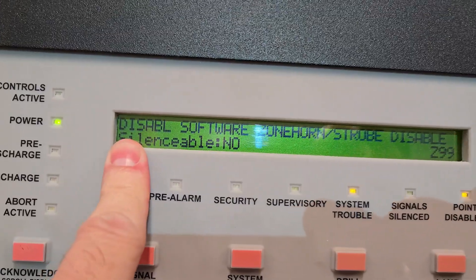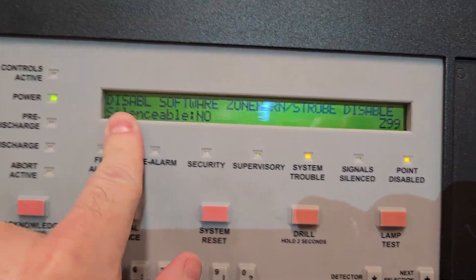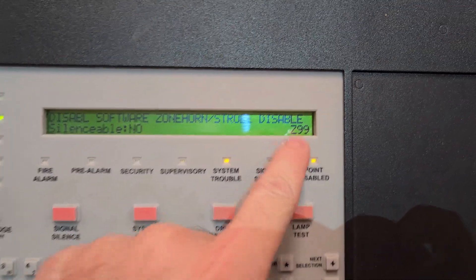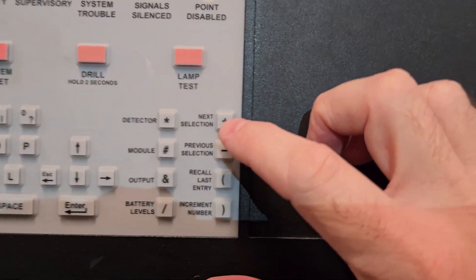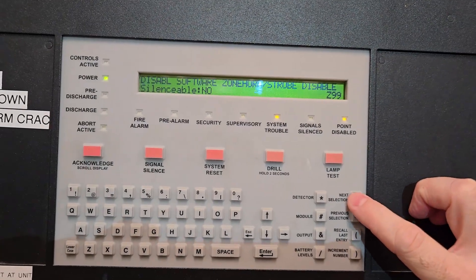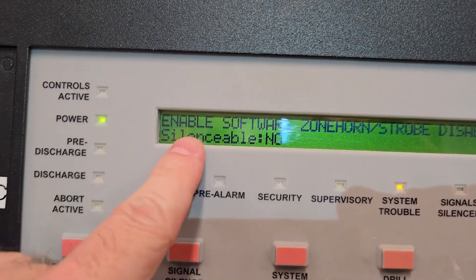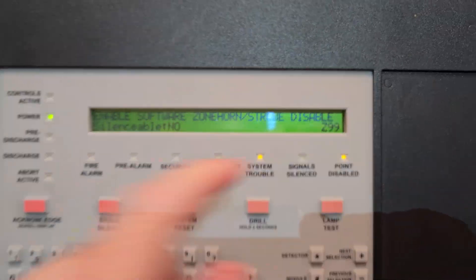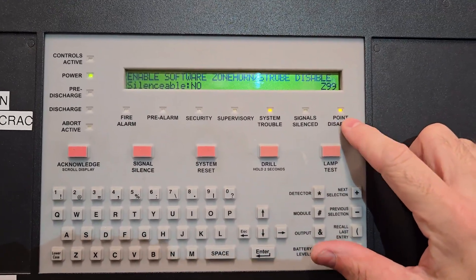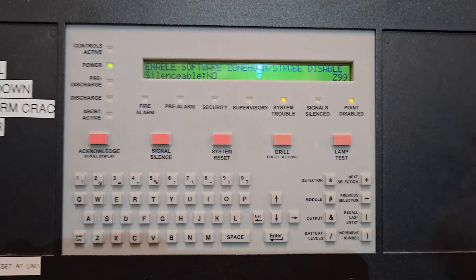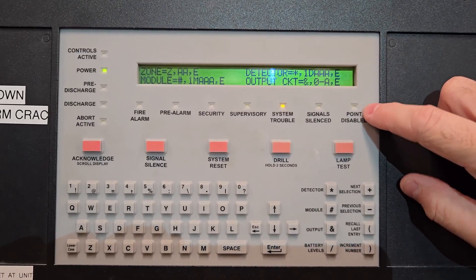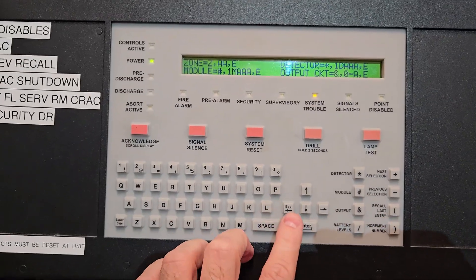Now you can see it's flashing 'disable' because we currently have it disabled. If it were enabled it would say 'enable,' but it's disabled and we have 'point disabled' lit. I hit the Next selection key to change it to enabled. Now it says 'enable — software zone 99.' The last thing I do is hit Enter, and you're going to see the 'point disabled' light disappear because it's no longer disabled. When I hit Enter that light went away, and it brings me back to the menu.